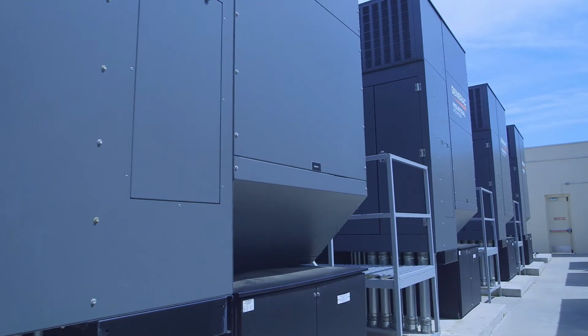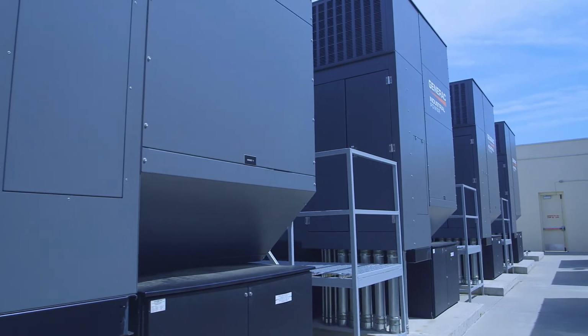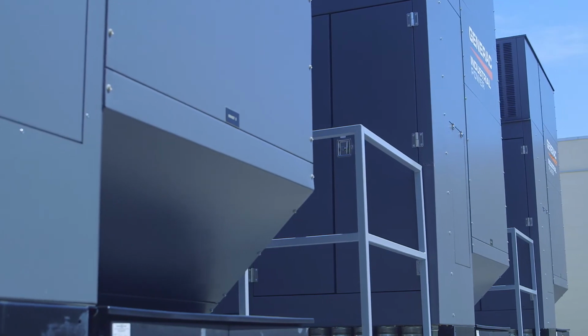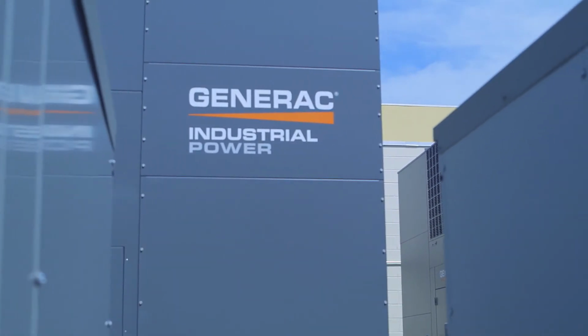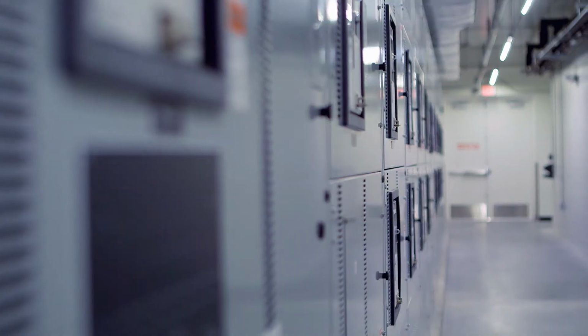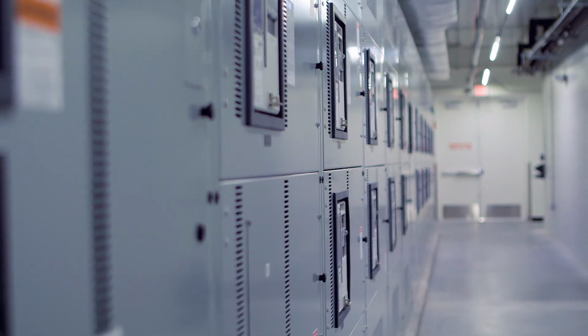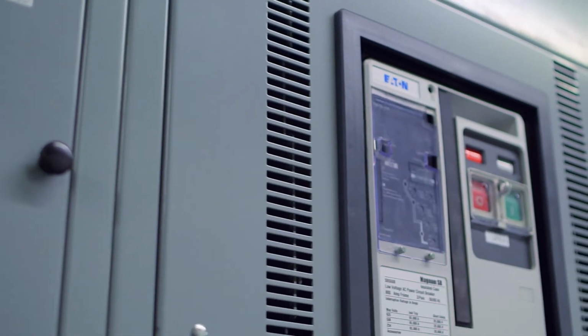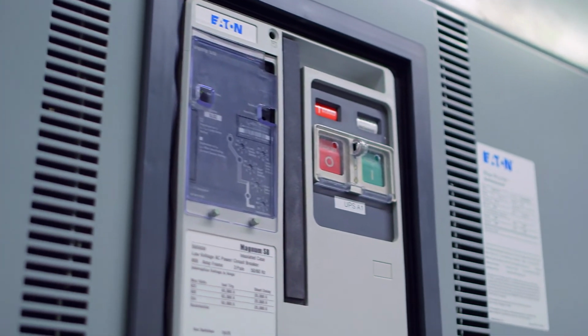We have 4 1-megawatt generators here. We need 3 to get our 2.4 megawatts of load to power the facility, plus an extra for N+1 redundancy. For further redundancy, each generator contains 2 500 kilowatt engines. In the event of a utility power outage, our UPS platform holds the load while the generators start, which typically happens in a matter of seconds.